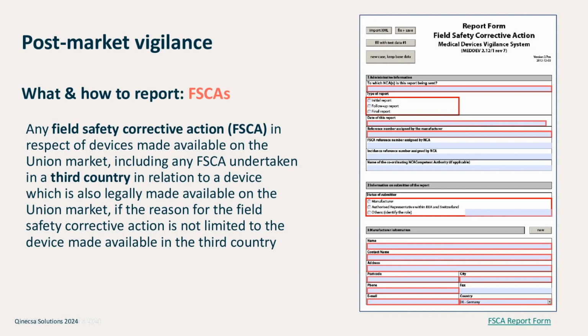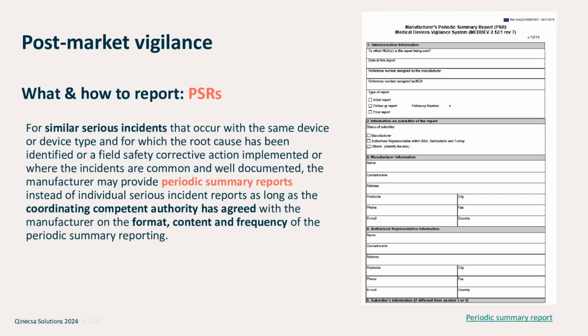It's a safety action that is done if there is a safety issue with the device. That includes an update of safety information that is distributed with the device, which is the instructions for use. For pharmacovigilance departments, there is a relevant component in the need to monitor field safety corrective actions that occur in third countries. This is something that would be typically specified in agreements with the manufacturer, who is ultimately responsible for the whole system and reporting.